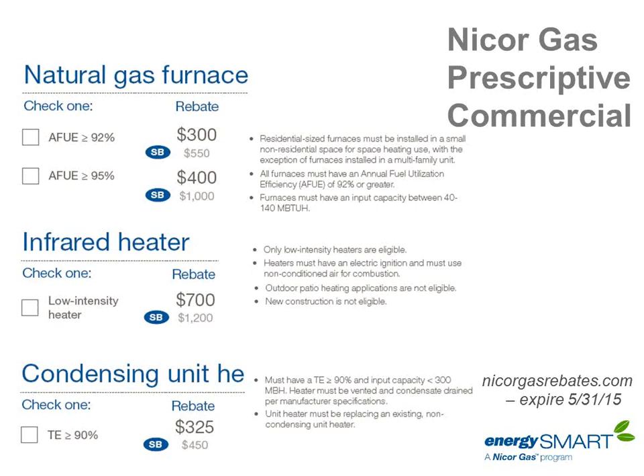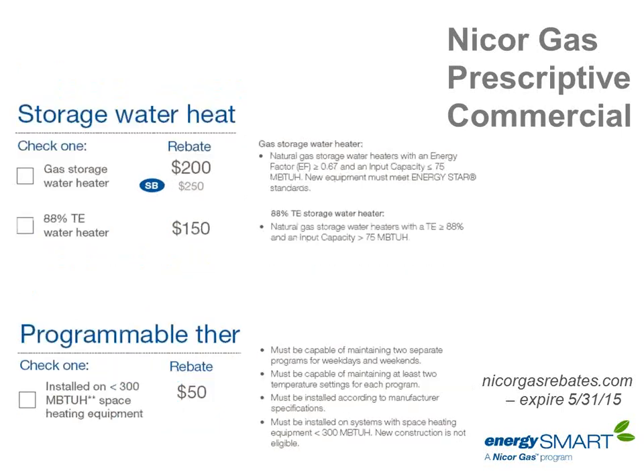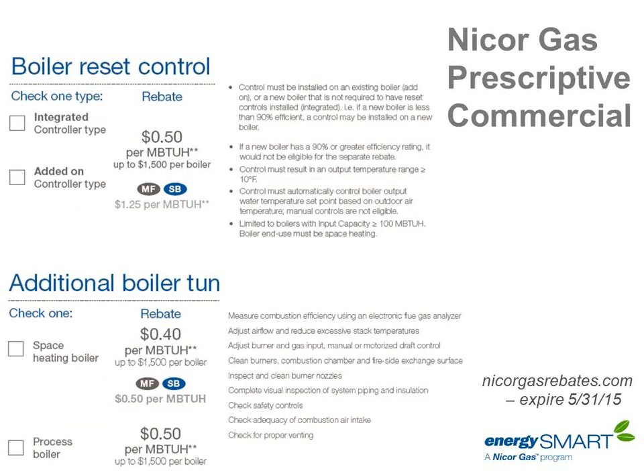Condensing unit heaters have a rebate with a bonus for small businesses. Storage water heaters, also rebatable. Got to be a 0.67 for a smaller heater under 75,000 BTU input, and you got to be 88% thermal efficient for the larger ones. By the way, energy factor and thermal efficiency have nothing to do with each other, 2 unrelated tests. So that's why the dollar amounts and stuff all seem a little weird when you look at them visually.